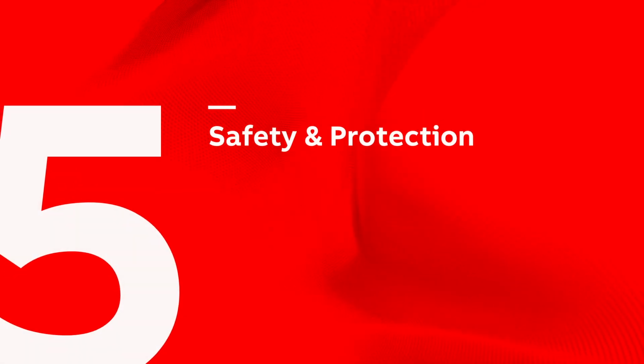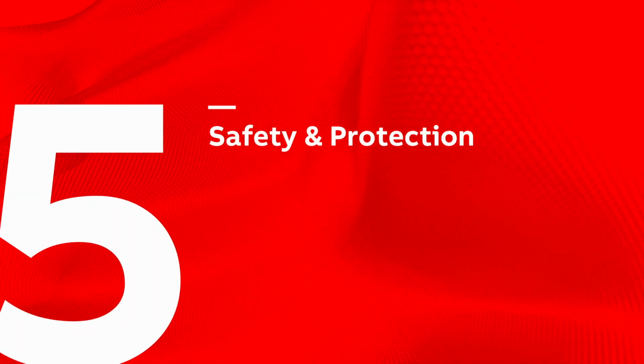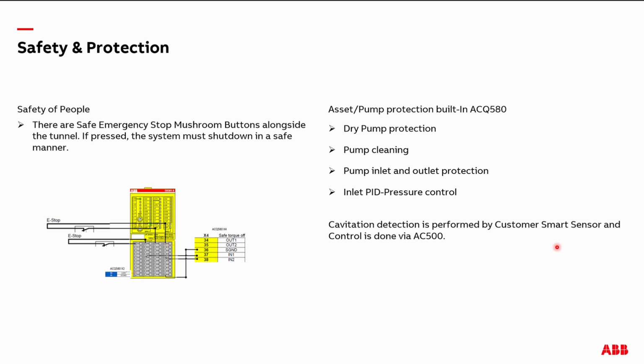So this is already the last slide now. Just to have a look, what are the safety and protection functions which are important and installed in the slurry pumping plant. From the safety side, across the tunnel, there are safety emergency stop mushroom buttons alongside the tunnel, and these are all connected to the fiber optic infrastructure in the tunnel. So that's where we have a strong point as well. Our ProfiSafe and Profinet can be connected via any kind of infrastructure, as long as it's Ethernet based, we can run Profinet and ProfiSafe on top of it.